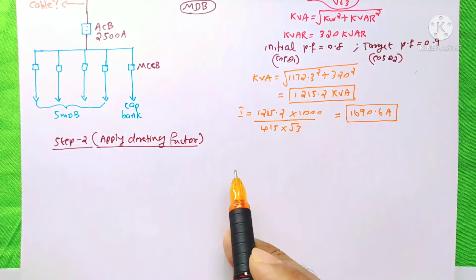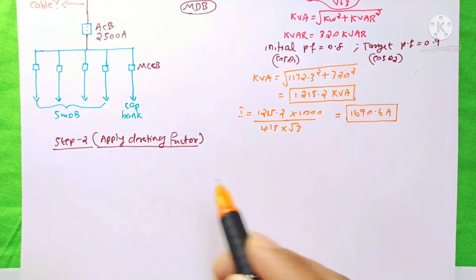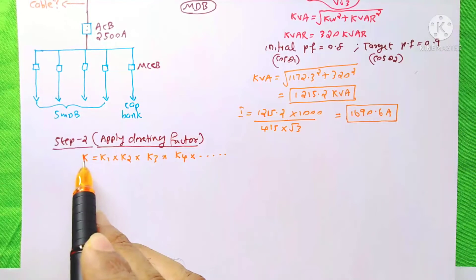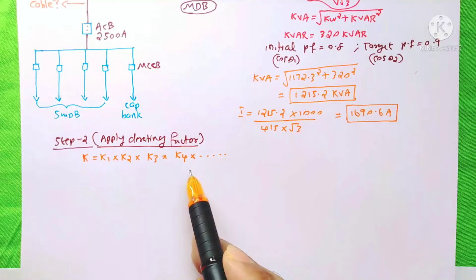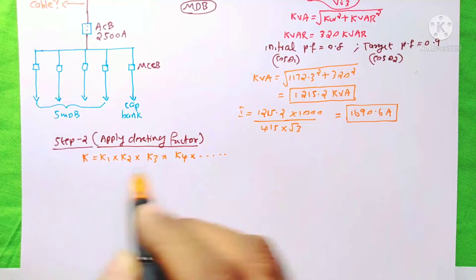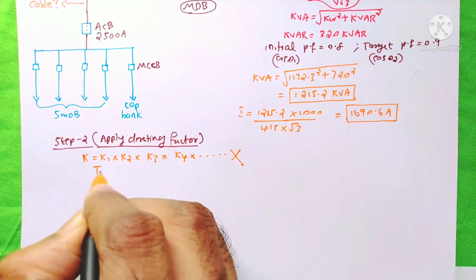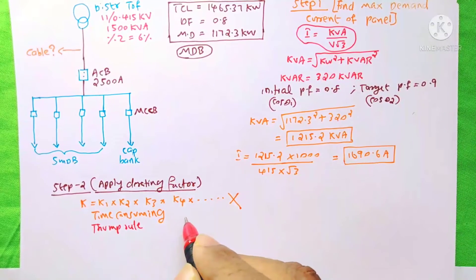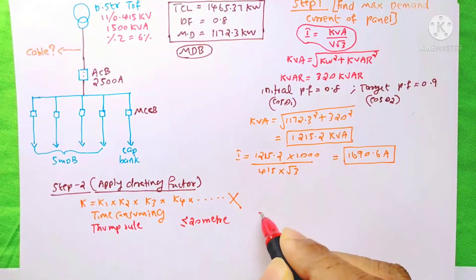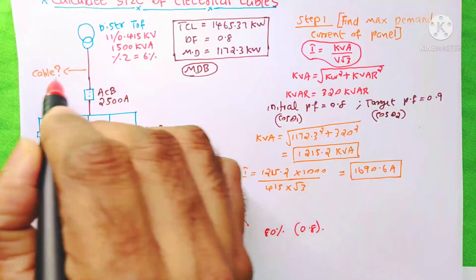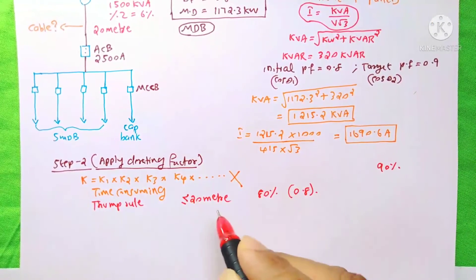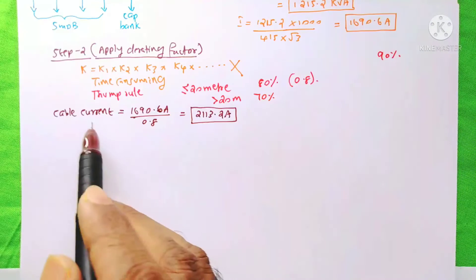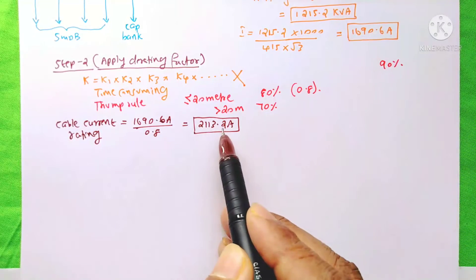The next step is applying the derating factor. The derating factor depends upon the cable route. As a practical thumb rule: if the cable length is less than or equal to 20 meters, consider 80% derating factor. The cable length here is 20 meters. If the cable length is more than 20 meters, consider 70% derating factor. Applying the 80% derating factor gives a derated load current of 2113.2 A.